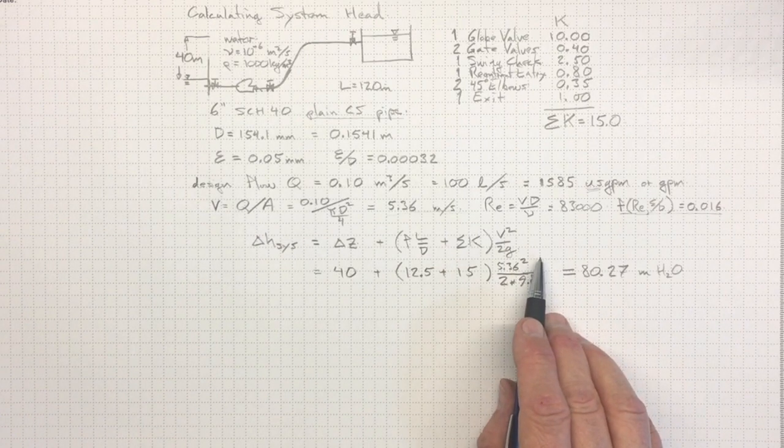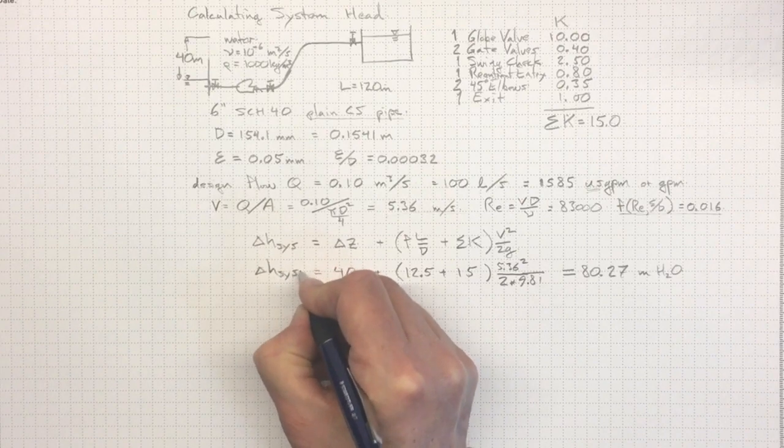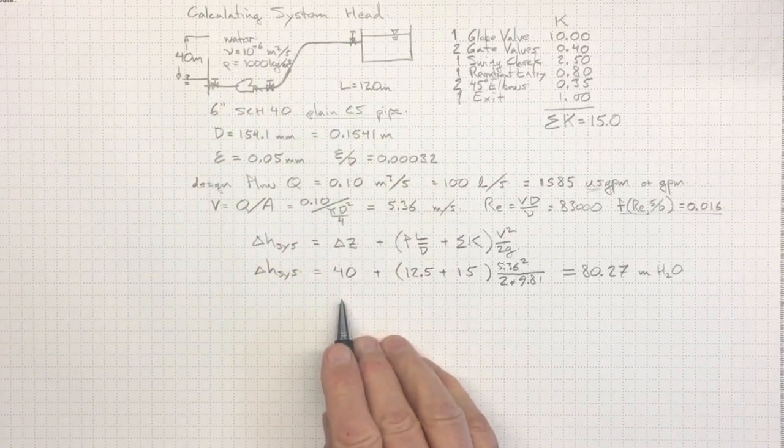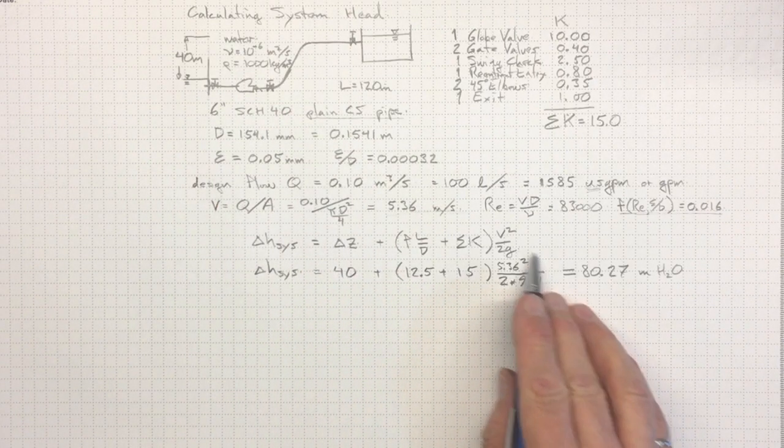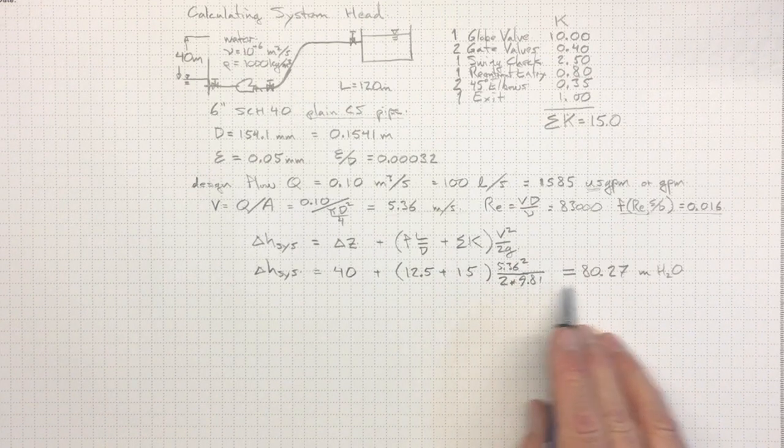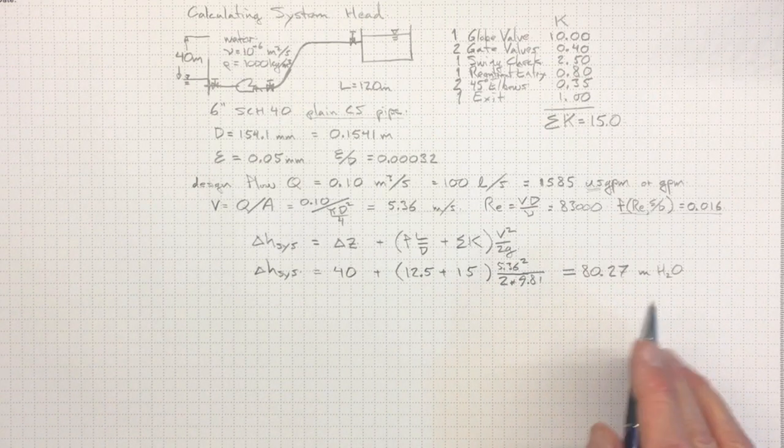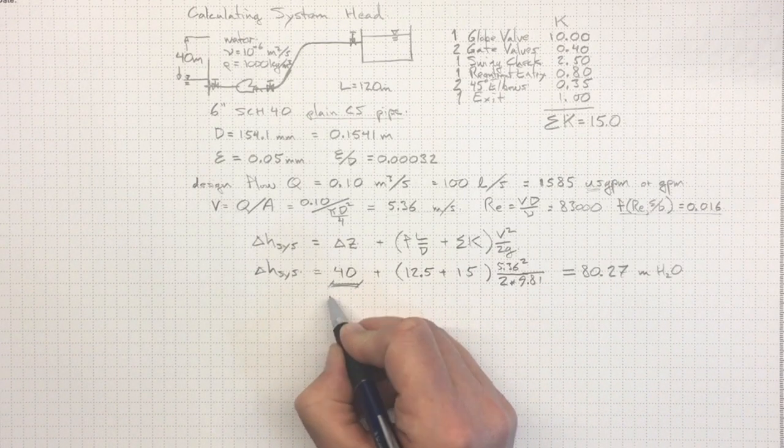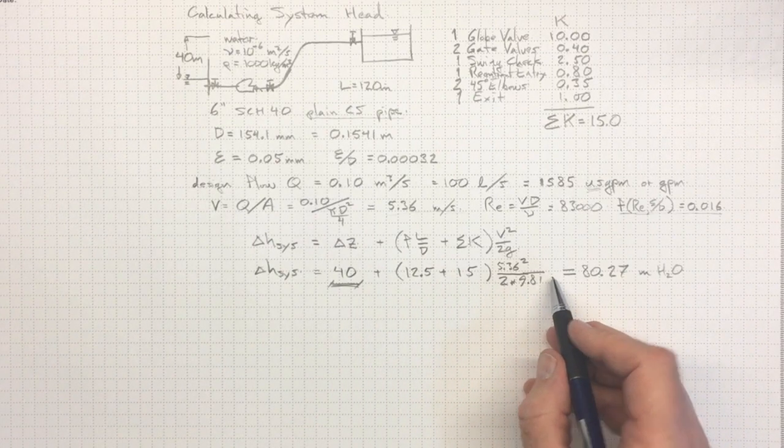So, let's look at that for a moment. This delta H sys, the work that I'm going to have to get the pump to do to raise the head across the pump, it's going to be 40, plus 12.5, plus 15, times the V squared over 2G. It's going to give me about 80.27. So, about half of that is overcoming the elevation and doing useful work. And the other half, roughly, is going into losses.